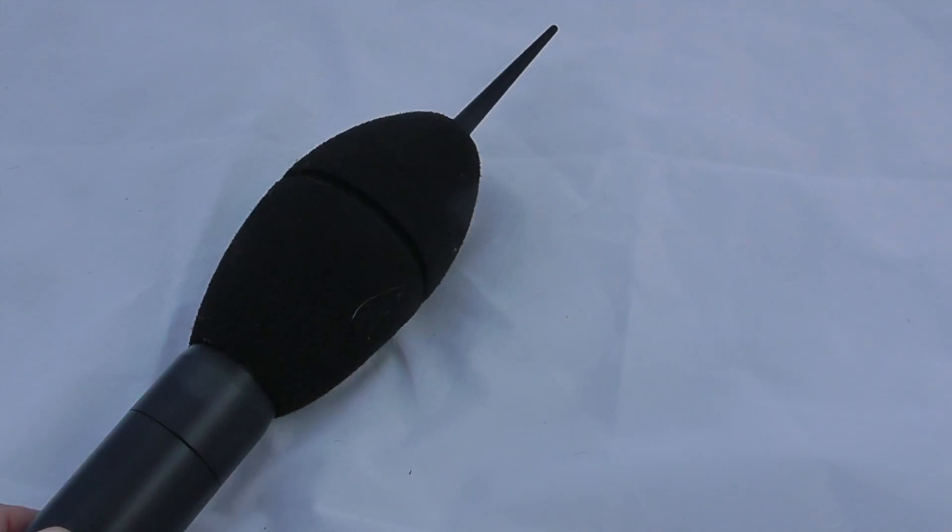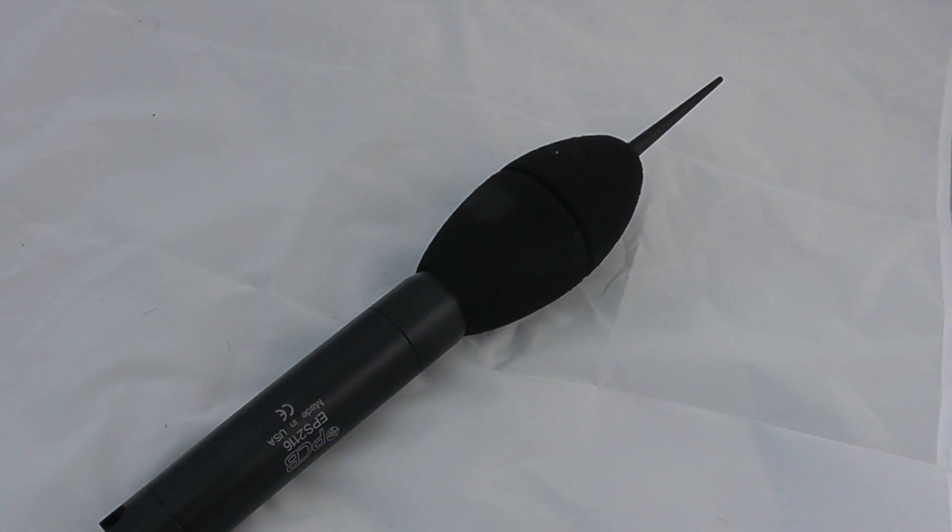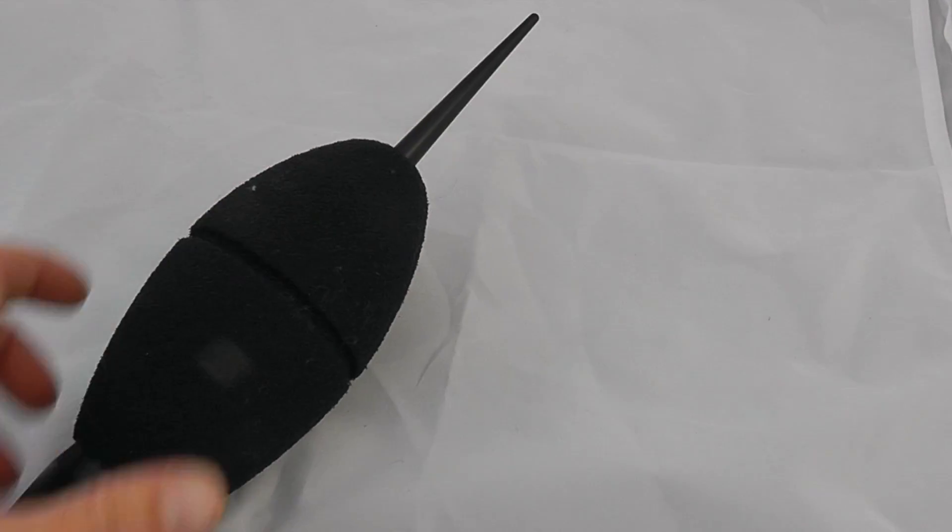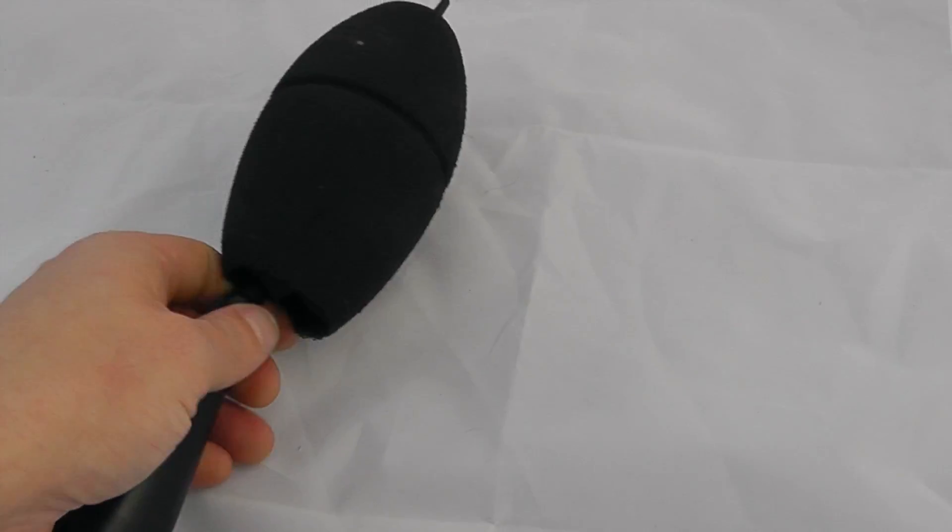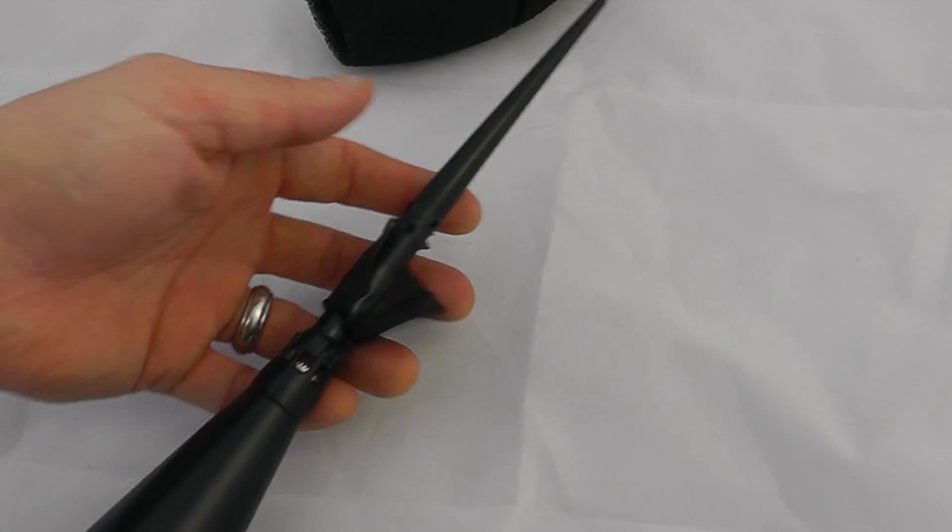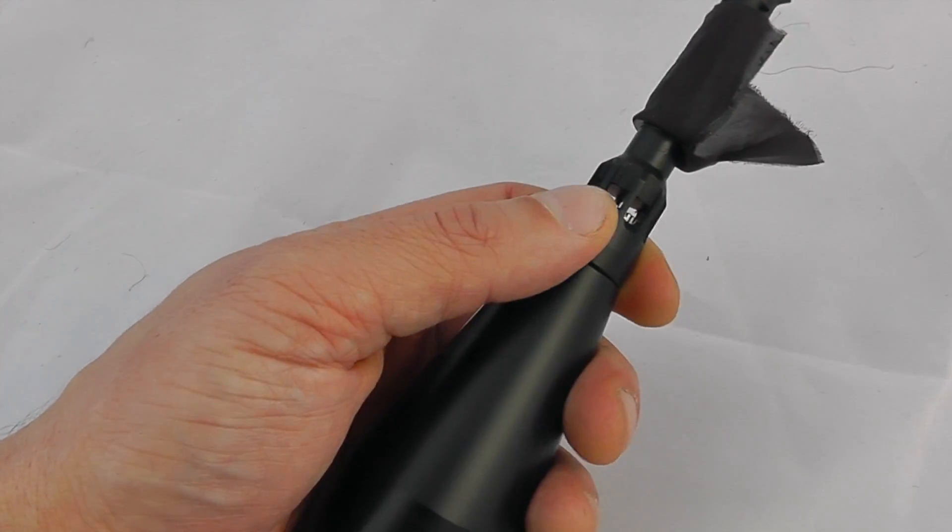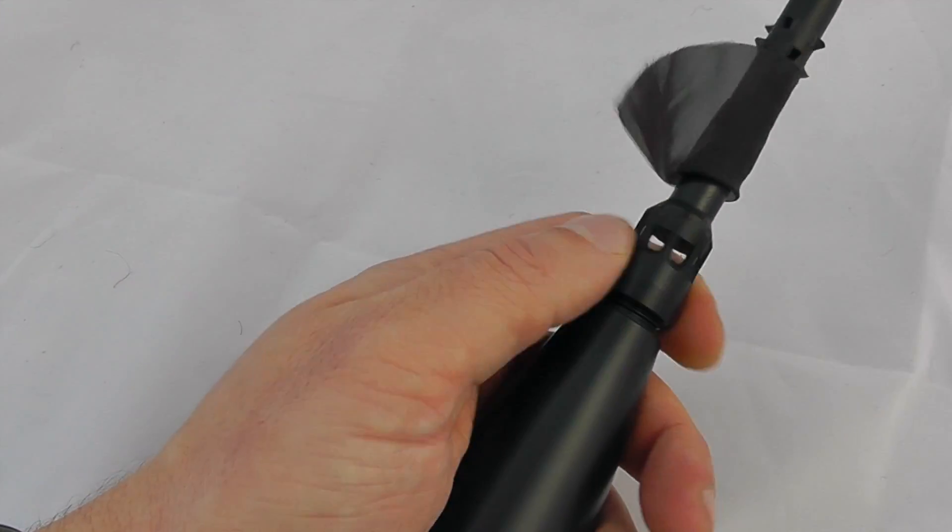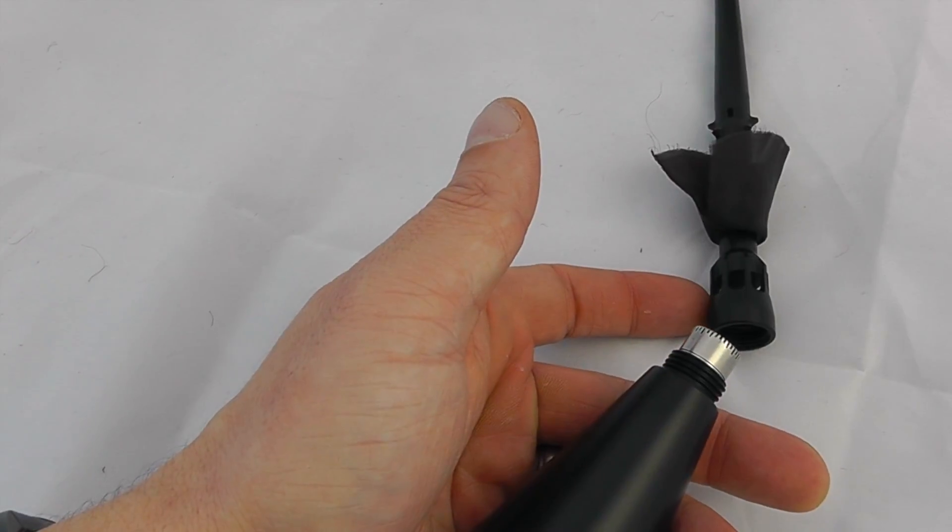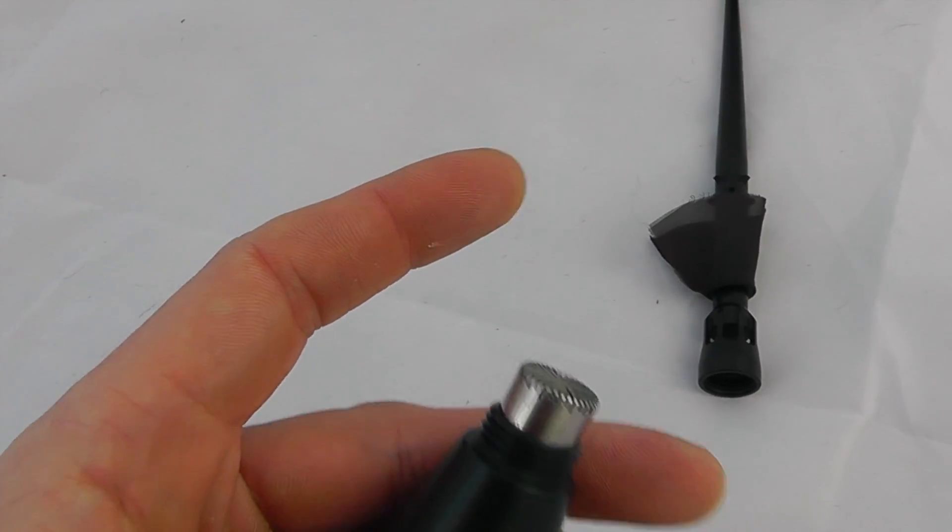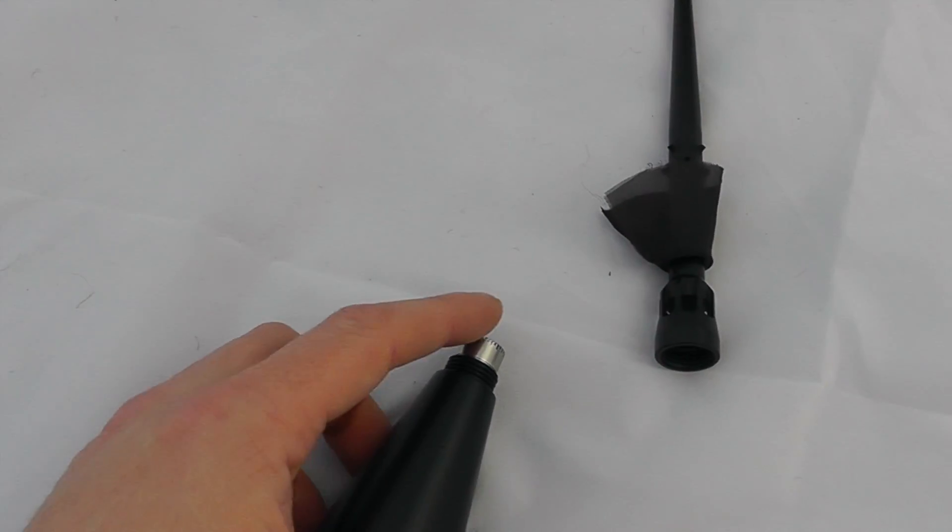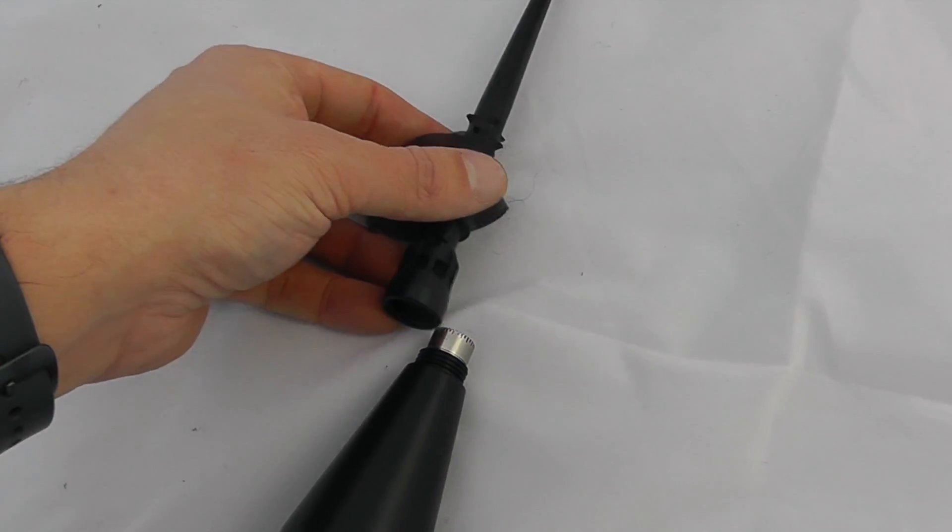To conduct calibration, we need to remove the extension cable and the cowl. First remove this section and then remove this top section. This unscrews and then the microphone is exposed. We can apply an acoustic calibrator to the end of the device and then reassemble.